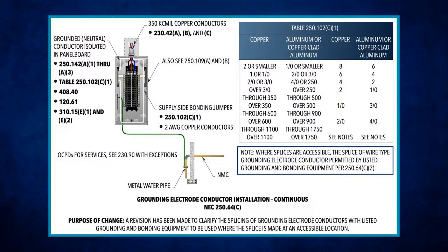So if I'm looking at this, this is really good. All of this is based on where I'm going to. Where? Building steel or a cold water pipe. And y'all have heard me say this before, when you're going to the cold water pipe or building steel, you need to use the table for sizing these conductors. But when I'm going to a concrete encased electrode, a ground rod, or a ground ring, they have specific sizes to go to those. Okay.